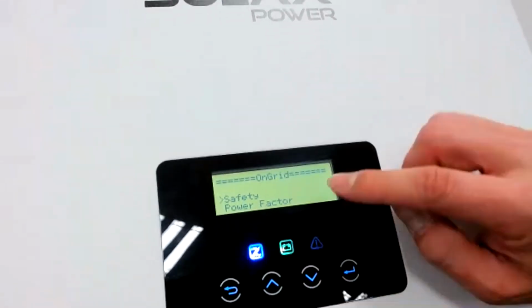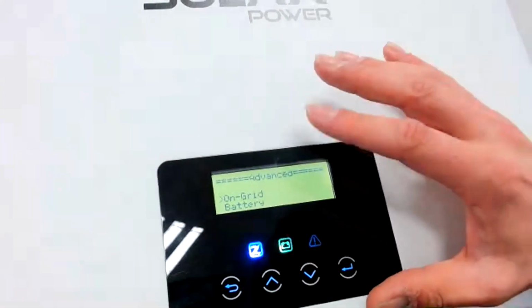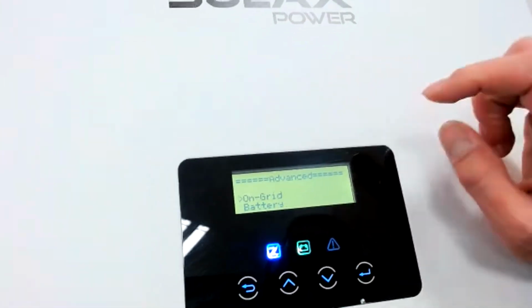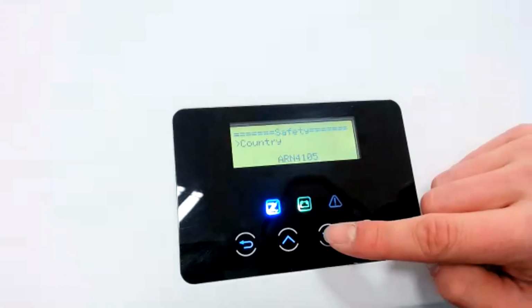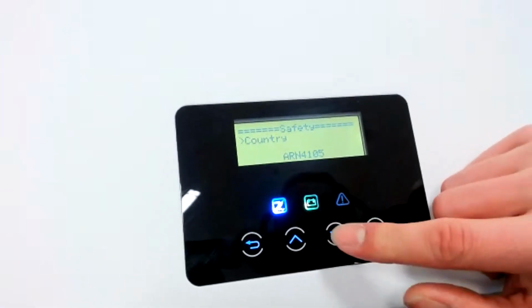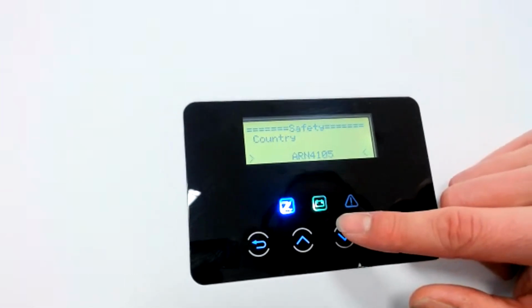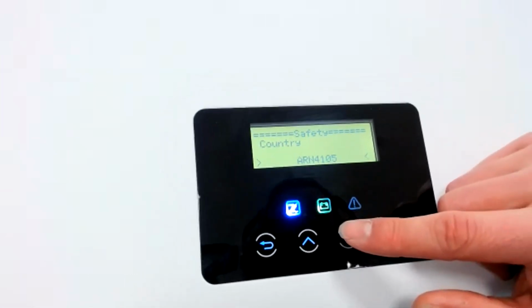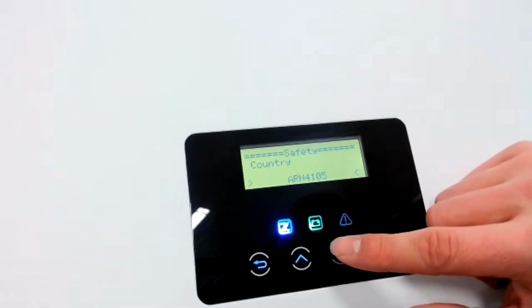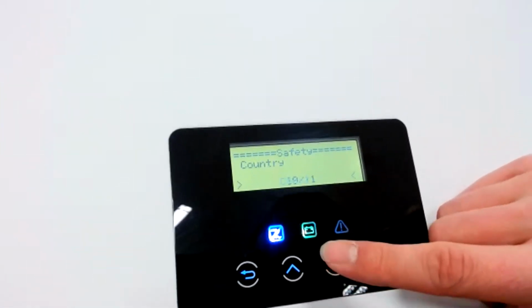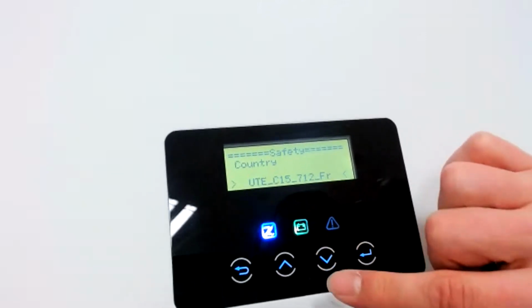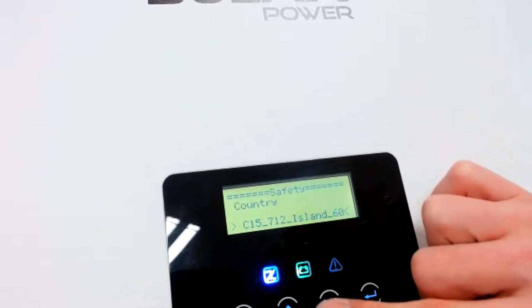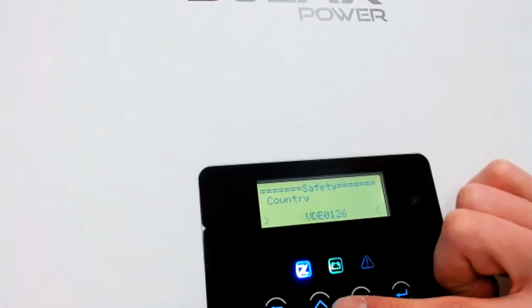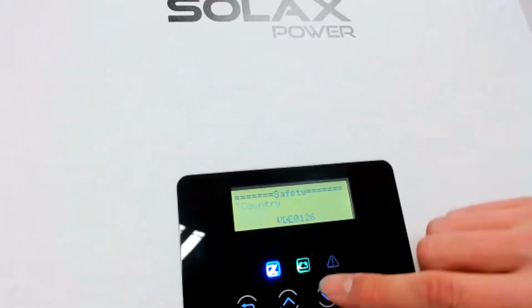On-grid is the part of the settings where you set everything related to the grid. Safety shows you the norm you have to set for your country. In Germany, for example, it's ARN 4105 or VDE 4105. Different countries have different settings, and you have to choose the right one, because depending on what you choose here, the grid parameters will be changed.